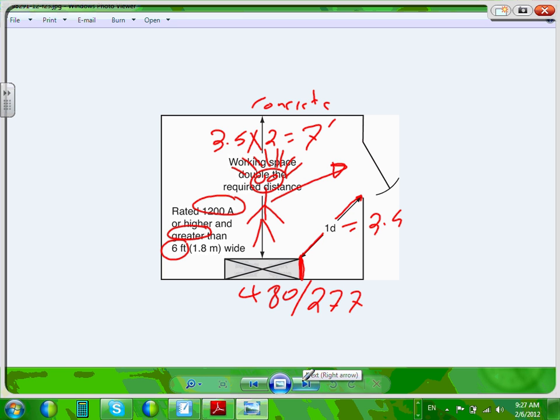You might laugh at these rules, guys, but it saves lives, and it's the law. Why is it important? When you orient your switchgear as a project manager, you can lose a career over there. You put a 4,000 amp switchgear in a room, and you don't adhere to that rule, because now you got into the room. Now you're going to situate your switchgear inside the room, right? That's your electrician. You're going to put your platform for the switchgear. You're going to put the first stick here, and the first side, make sure it's no further than 3.5. If you have large equipment, please review this. If you have anything 1200 amp or higher and more than 6 feet, that's switchgear. You have to pay good attention to this. Any question, guys? Can I have thumbs up? Make sure, Chad, we got that one. Okay.